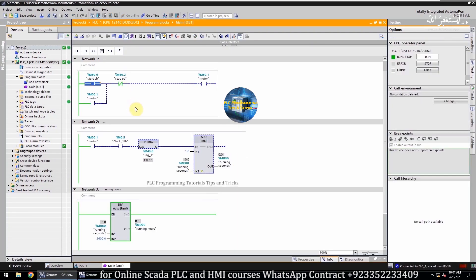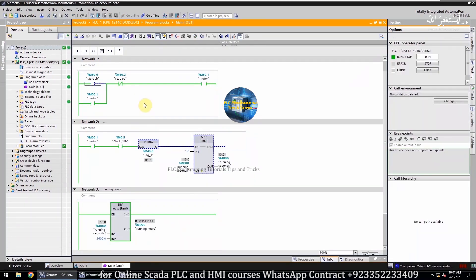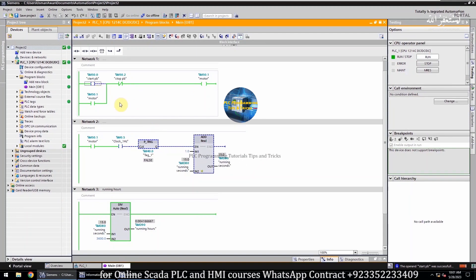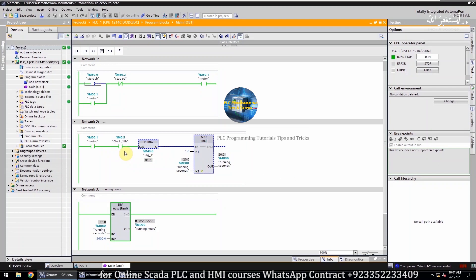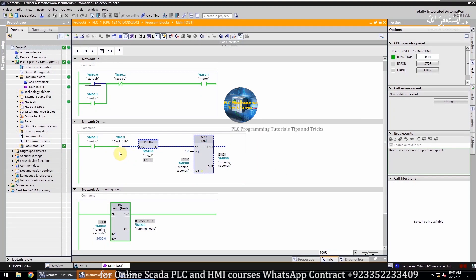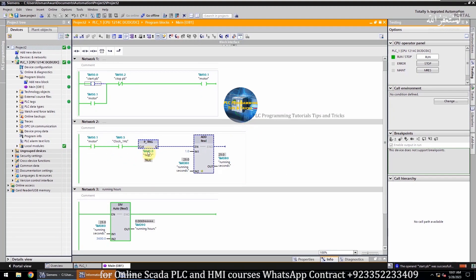Let's turn on the motor by turning on the start push button M50.0. In network 2, as the motor turns on, the M50.1 contact closes, and on each rising edge of the clock bit M0.5, the add instruction increments the running seconds by 1 second.